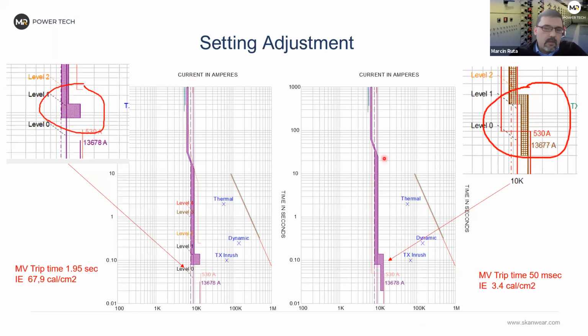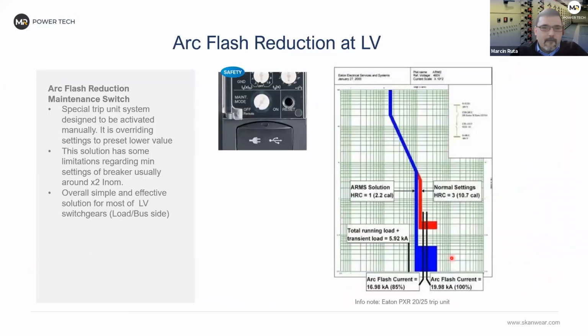What I found was, okay, maybe we can also modify the medium voltage side, one step ahead, going upstream. And there is a reason why I show it here. You may see there's a zoom. I dropped the settings on the medium voltage relay very low, and this is obviously not selective. This will cause a problem with the transformer starting due to inrush current, so we cannot use something like this. But we know that if we keep it, we'll go below 3.4 calories. So that's a very big difference. And now I'll come back to this example in a minute.